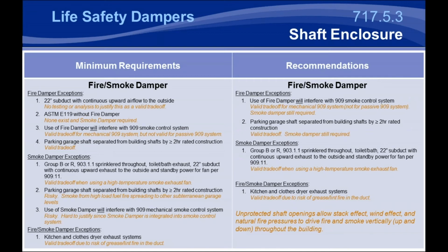Now, while it is likely that there isn't going to be massive fire going up and around this 22-inch subduct, if you want to use that subduct to remove the smoke damper requirement, you are required to have an exhaust fan that has continuous standby power, and you've got sprinklers throughout the building, and you're using it as, say, a toilet or bath exhaust. Of course, this is an exhaust out at that point, but the problem is the code is silent on requiring a high temperature fan. So you could have a failure of the fan that stops exhausting that smoke out of the building, and then potentially smoke can linger in this exhaust duct. So basically, as long as there's standby power, standby generators, and a high temperature smoke exhaust fan, we think it's a valid trade-off. Unfortunately, that may add additional cost, and we think maybe a fire smoke damper may be a less costly option.